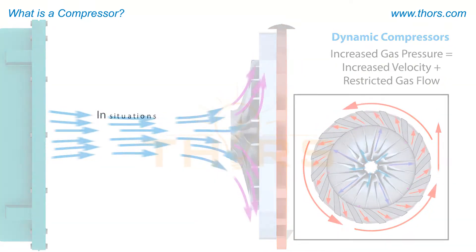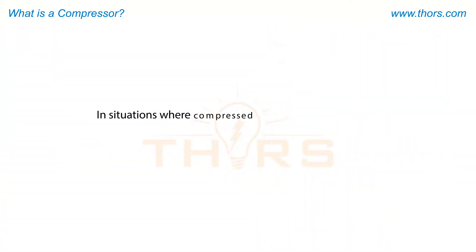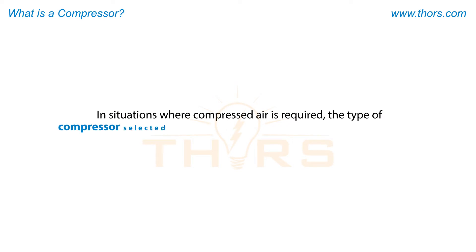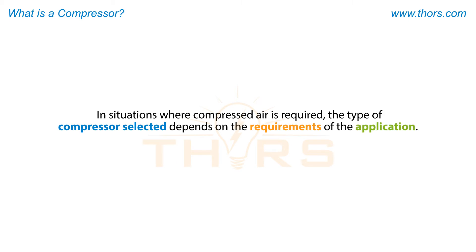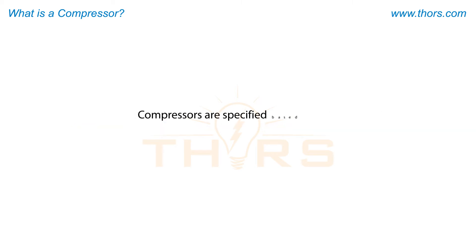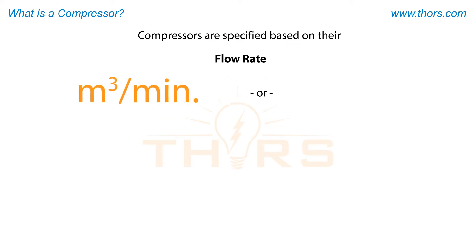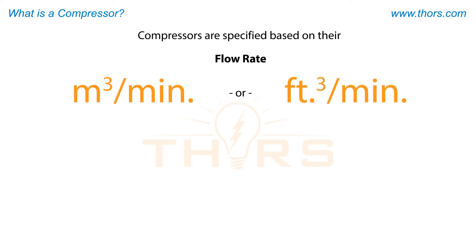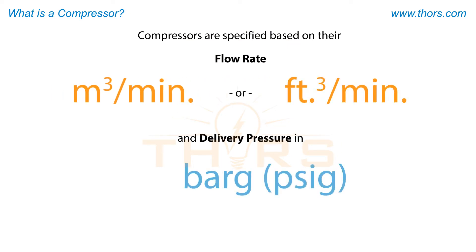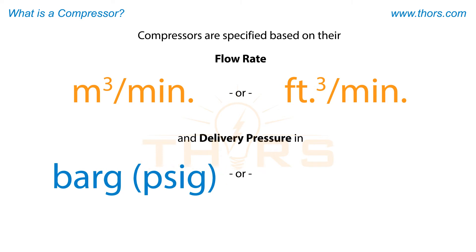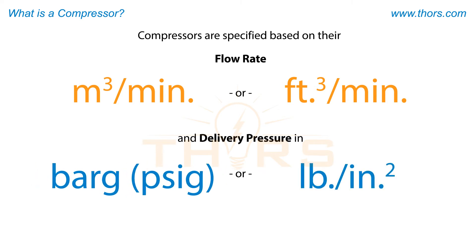In situations where compressed air is required, the type of compressor selected depends on the requirements of the application. Compressors are specified based on their flow rate in cubic meters per minute or cubic feet per minute, and delivery pressure in bar gauge or pounds per square inch gauge.